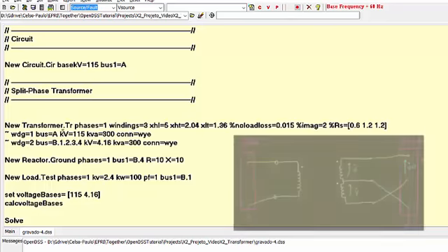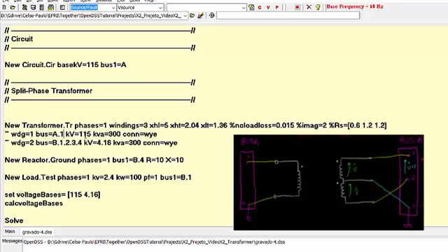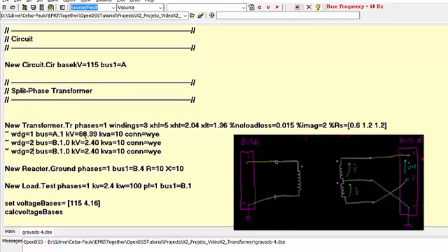The first winding is connected to node 1 of bus A and ground, so its rated voltage should be 66.39 kV. And let's set a rated power of 10 kVA. Let's assume that this transformer is supplying a 2.4/4.8 kV system. Then, the rated voltage of the second and the third windings should be 2.4 kV. Pay attention to the bus specification. They are responsible for setting the polarity of each winding.